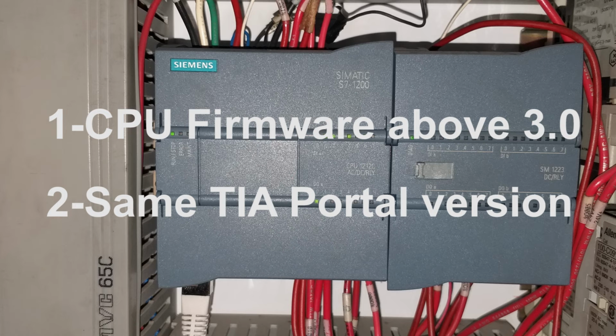The second thing is that you should have the same TIA Portal version installed in your laptop or PC as used by the programmer who created that project the first time or while installing this machine. For example, I am using TIA Portal version 13 today because the program which is uploaded in this PLC was created in TIA Portal version 13.